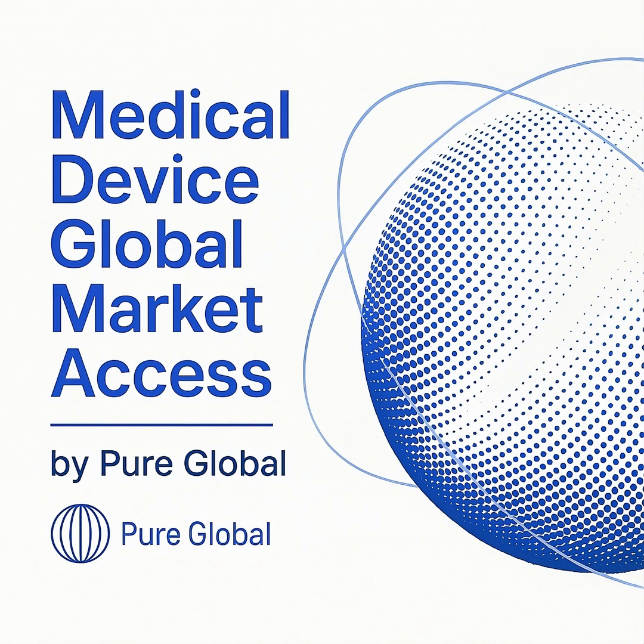Key steps in the FDA process include device classification, the submission of the required documentation, such as a 510(k), PMA, or an investigational device exemption, IDE, ensuring compliance with FDA Quality System Regulations, QSR, and undergoing facility inspections and audits. Upon successful review, the FDA issues a clearance or approval letter. It is also worth noting that FDA registration is a separate process from device approval and simply indicates that the manufacturer is registered with the agency.